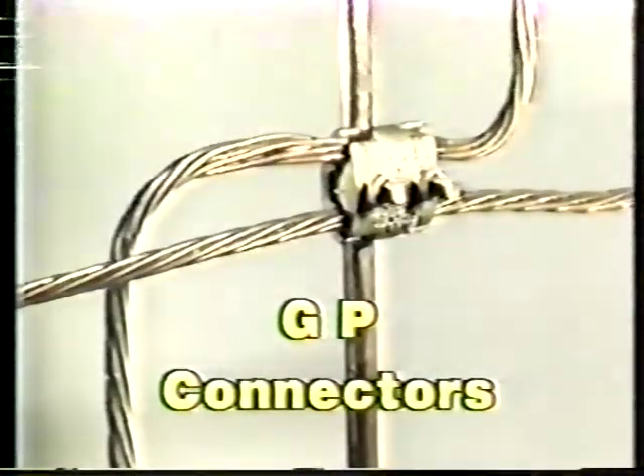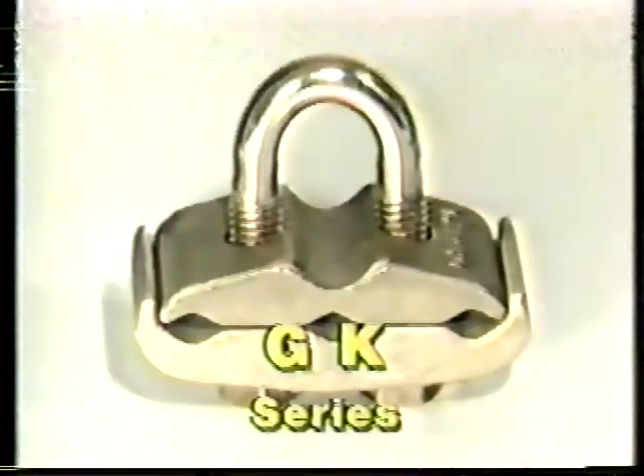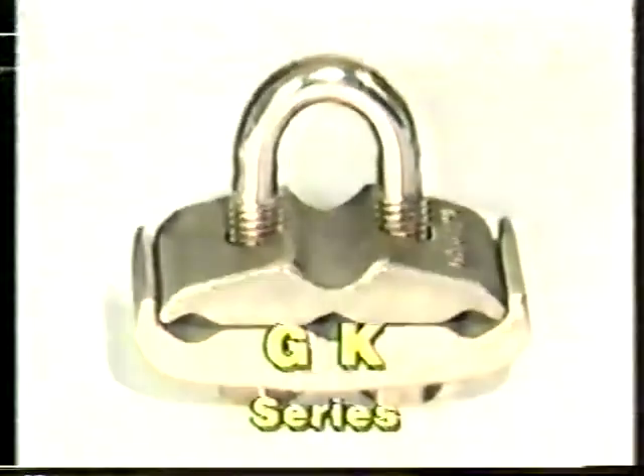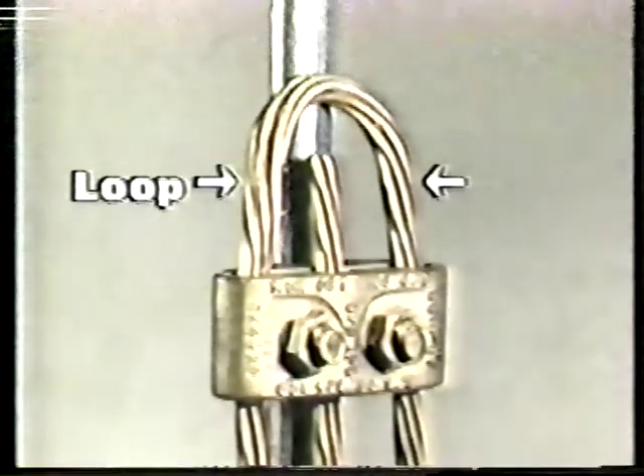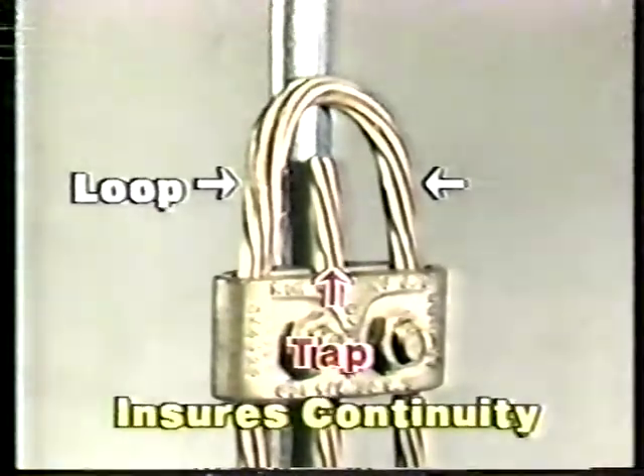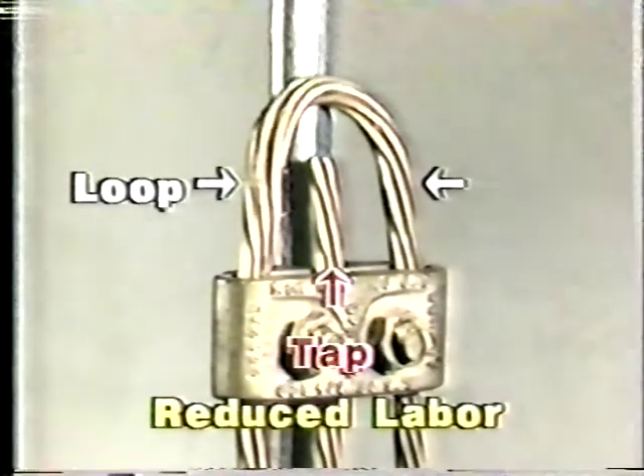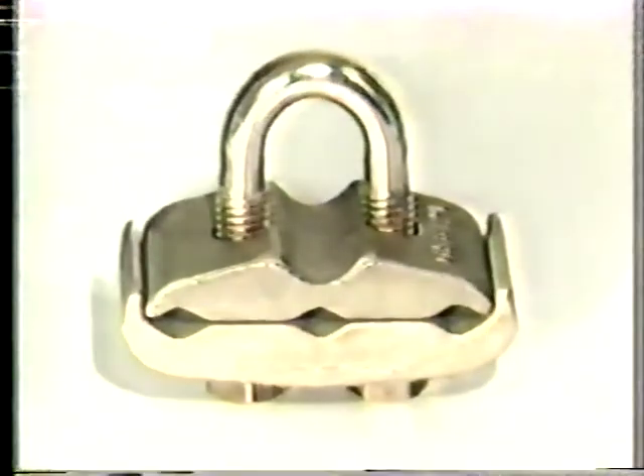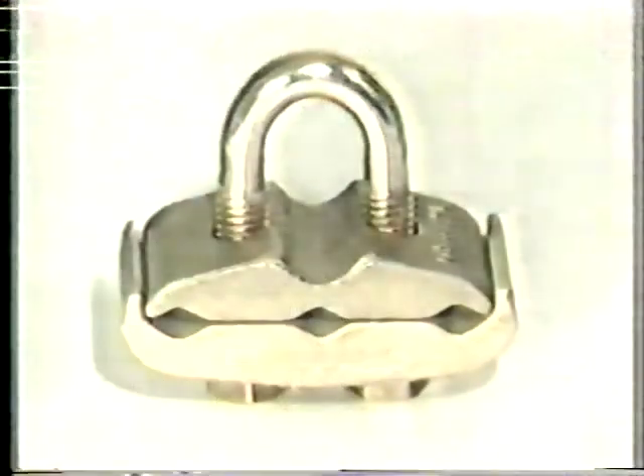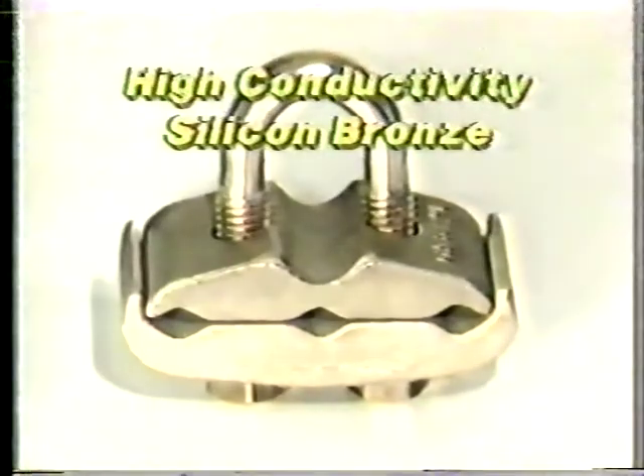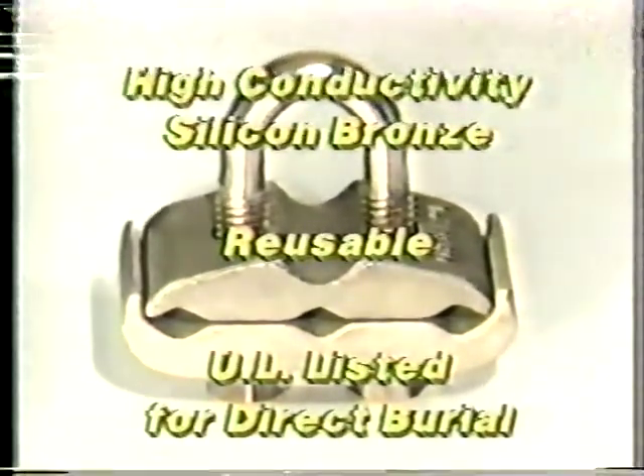GP connectors can also be used in a ground grid application by connecting 2 conductors to a ground rod at a cross connection. The Burndy GK series provides you with a means to connect 3 equal copper cables to a rod or tube. Using GK connectors, a loop can be run through the outer grooves, and an additional cable can be connected in the center groove to serve as a convenient tap. Since the looping cable can be attached without cutting, continuity is ensured and installation labor reduced. As shown in the Burndy catalog, these connectors are range-taking and available in models to handle a wide range of copper conductors and pipe diameters. They are made of high-conductivity silicon bronze, are reusable, and UL listed for direct burial installations.